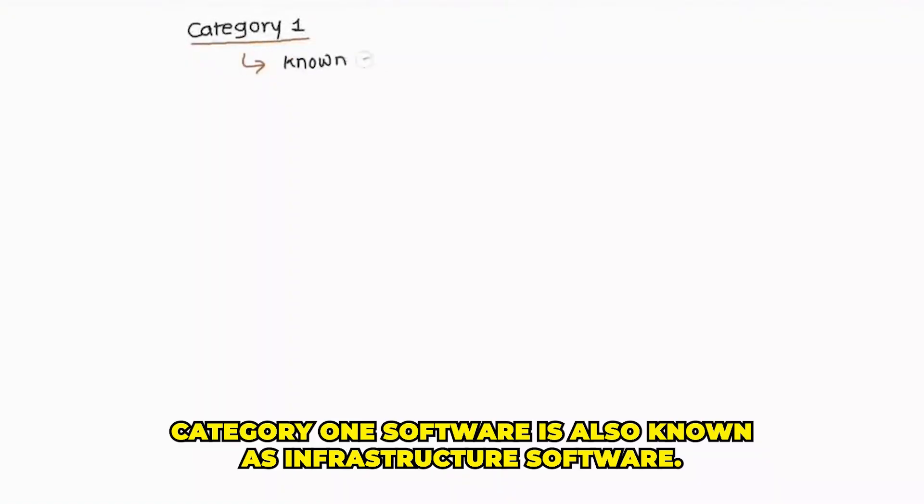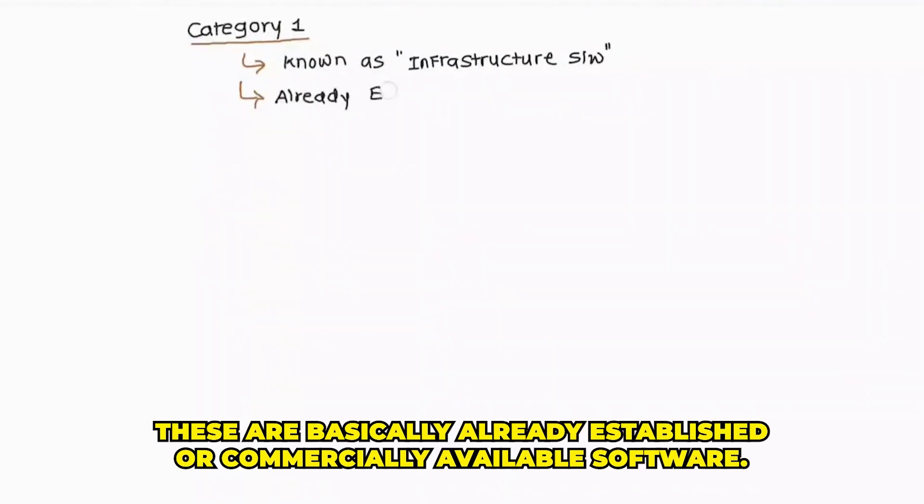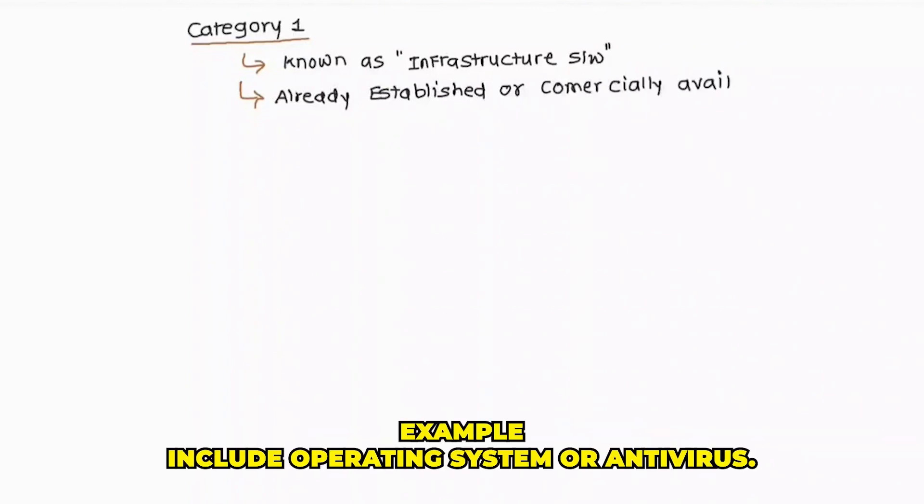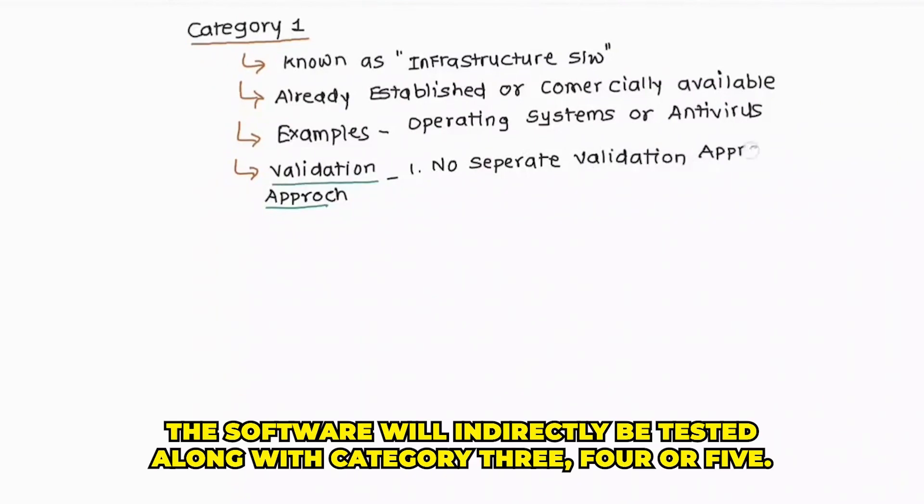Let's see one by one what these software categories are. First is category 1. Category 1 software is also known as infrastructure software. These are basically already established or commercially available software. Examples include operating systems or antivirus. There won't be any different validation approach for this category. Instead, the software will indirectly be tested along with category 3, 4, or 5.